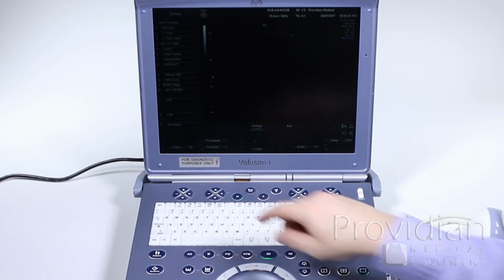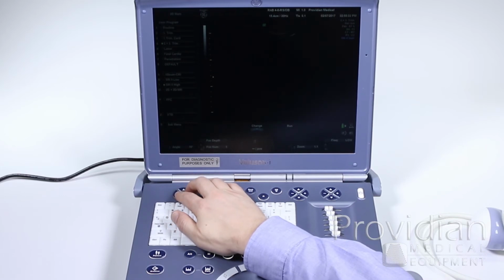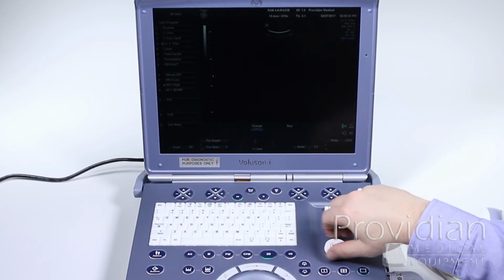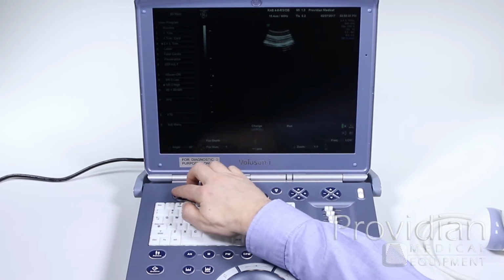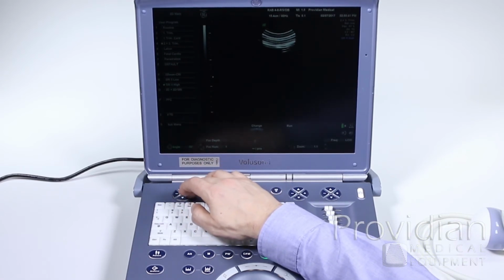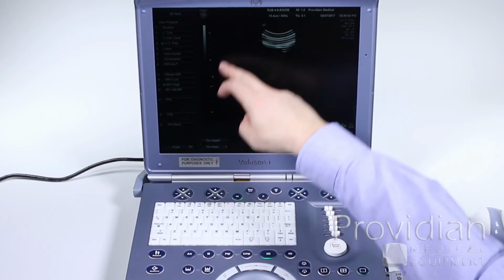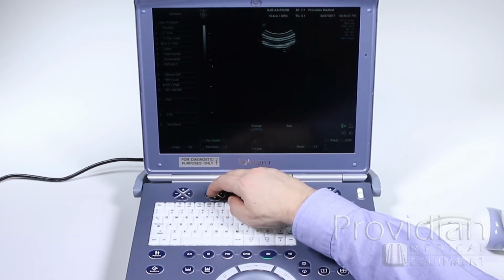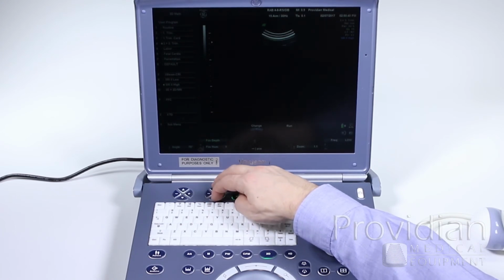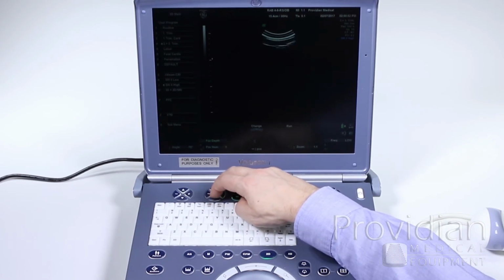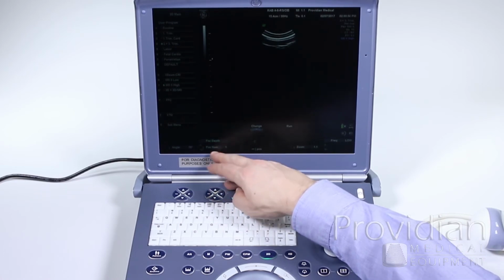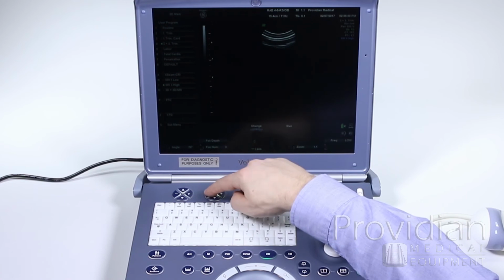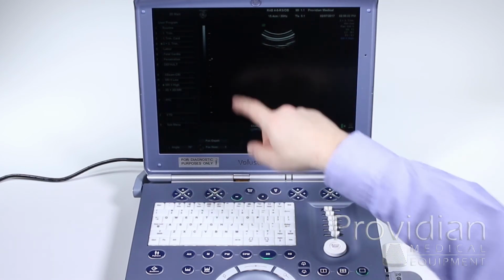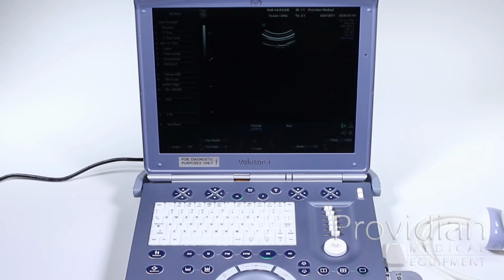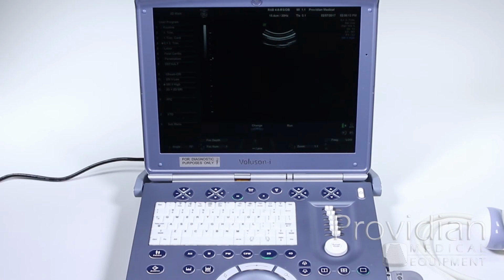You can change some of those here. You have your angle here, this will change the angle of the sector in 2D mode. Focus depth. Your focus depth right here is a little triangle showing you the focal zones and where you want the image to be focused most clearly to make it the clearest. You can add focal zones, clicking left and right, 1, 2, and 3. And you do this to increase the area in which you want the ultrasound to create the best image. Note that when you do add focal zones, it will slow down your frame rate.